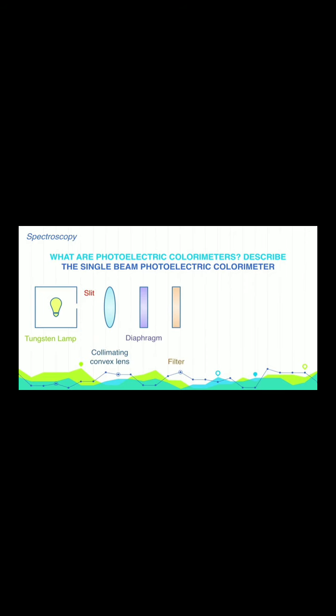Next comes the filter. It is a circular disc made up of a number of colored glass patches. When the light from the source is allowed to pass through the filter, the unnecessary radiations are absorbed and we get light of only one color. Next is the sample holder or cuvette. It is a rectangular, transparent container made of glass or quartz. Then comes the photocell. It is the component which converts the radiation into current.